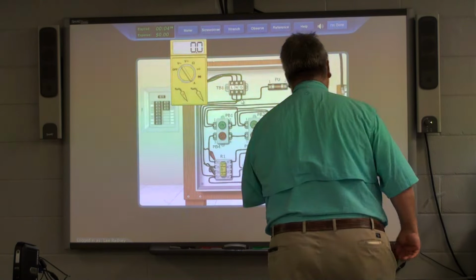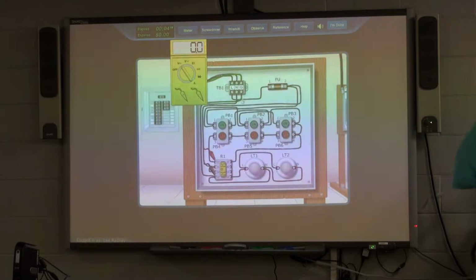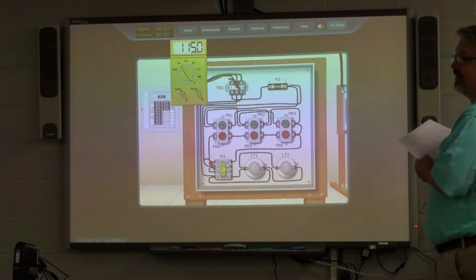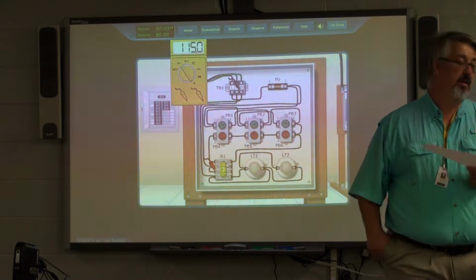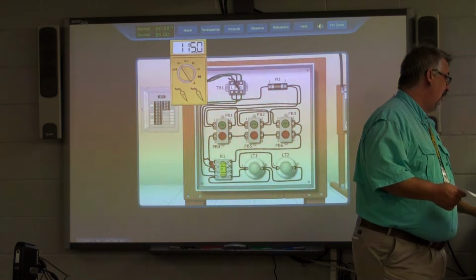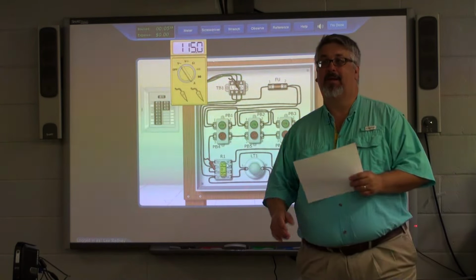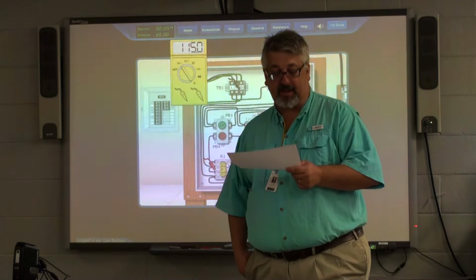Let's see if it is. So I'm going to put my black lead on the ground. Should read 115. Look at your wiring, that schematic diagram on the left. What do you think I'm going to read on pin 8 relative to ground? Should read 115. Cause that leg goes straight, comes down to pin 8. That's right, we've got a direct connection.